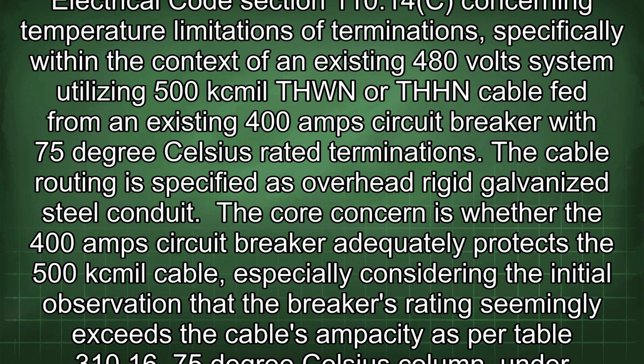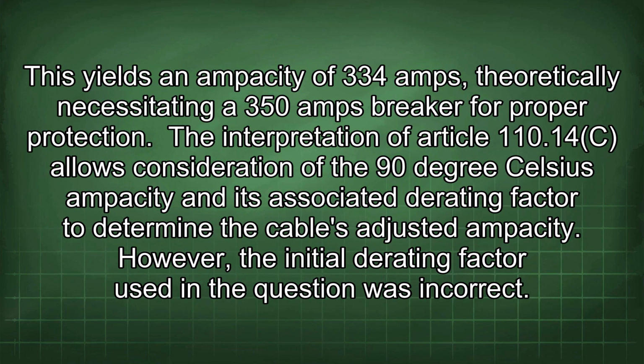The core concern is whether the 400 amp circuit breaker adequately protects the 500 kcmil cable, especially considering the initial observation that the breaker's rating seemingly exceeds the cable's ampacity as per Table 310.16, 75 degrees Celsius column, under a 40 degrees Celsius ambient temperature. This yields an ampacity of 334 amps, theoretically necessitating a 350 amp breaker for proper protection.